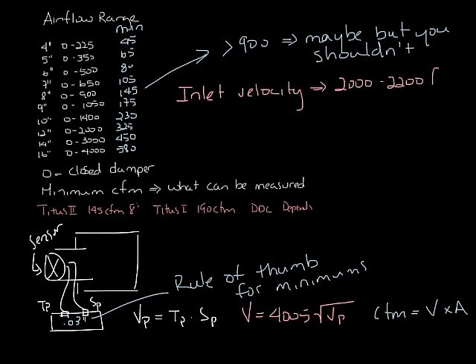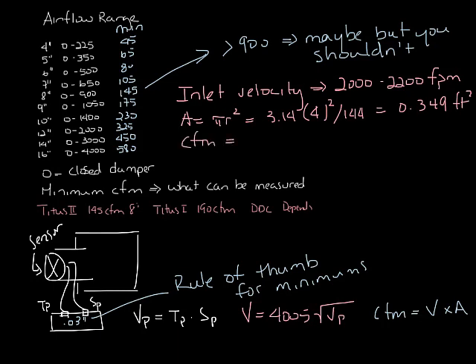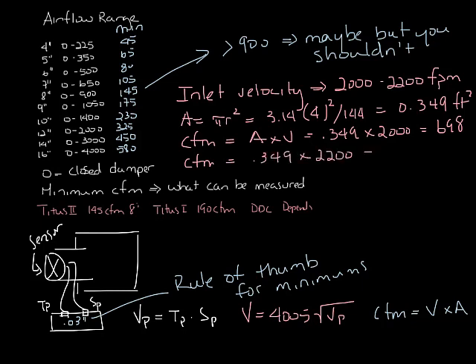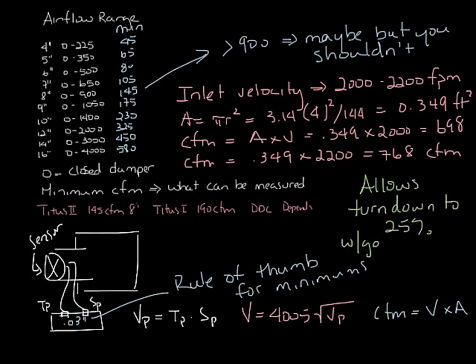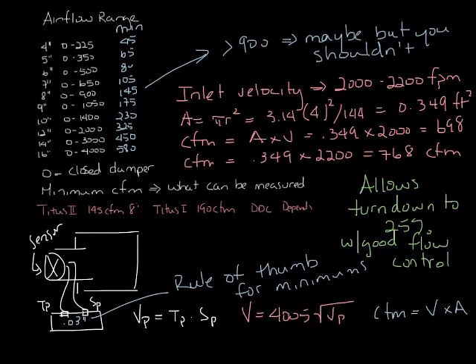So let's look at that 8-inch box again. The area of the 8-inch box is pi r squared, which is 3.14 times 4 squared divided by 144 to get into feet. That's 0.349 square feet. From there you can calculate the CFM at 2,000 feet per minute as being 0.349 times 2,000 or 698 CFM. Or at 2,200 feet per minute, which comes out to 768 CFM. And if you select your inlet size so that you're near the 2,000 feet per minute range, you'll also be able to turn your box down to about 25% airflow or 500 feet per minute and still be able to maintain proper flow control. So that explains how to size your primary air inlet.